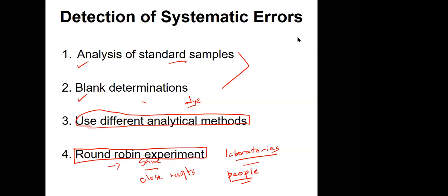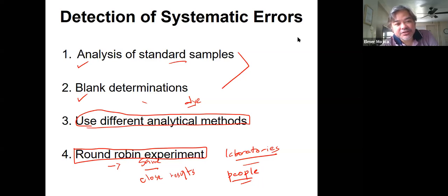But what if you have 20 people employed in a lab and they're not using the correct procedure? Has that ever happened? Yeah, it happens. Usually when you want to determine how accurate your instrument is, you really have to use a standard. You can use a standard that you prepare, or if you want one that is 100% certain, you can purchase a more expensive standard solution of whatever analyte you want to determine.